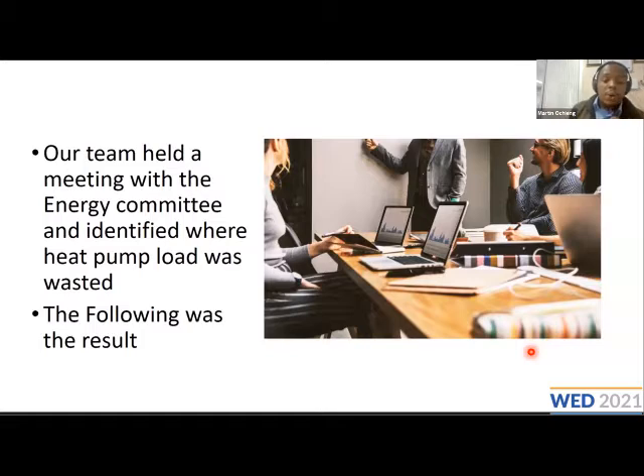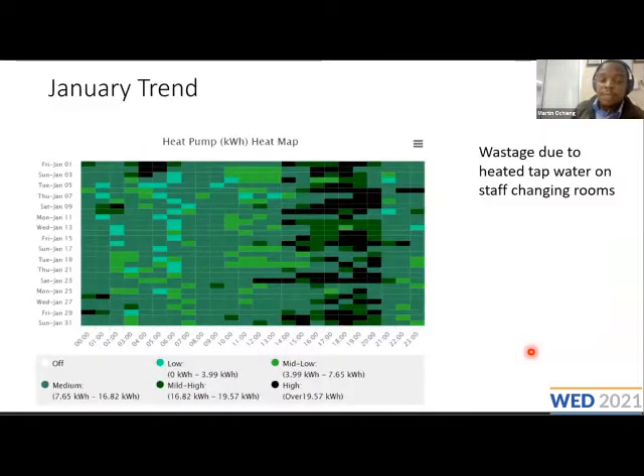So we were able to hold a meeting with the energy committee and identify specifically where the heat pump load was being wasted. And the following was the result. This chart here is what we like to call a heat map. Basically, it is a look into energy consumption per hour, maybe over a specific range. And as you can see, the darker shades indicate a larger energy consumption.